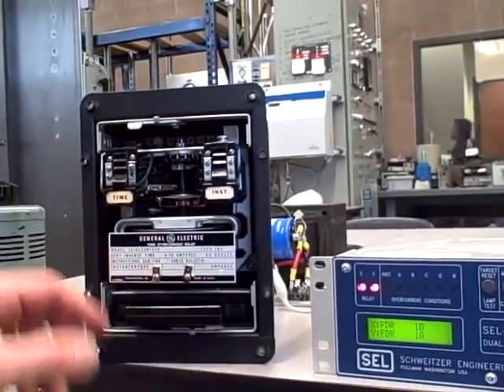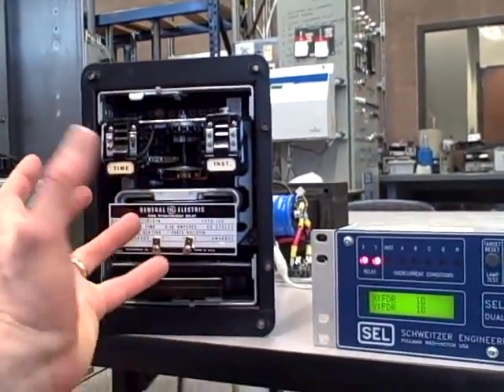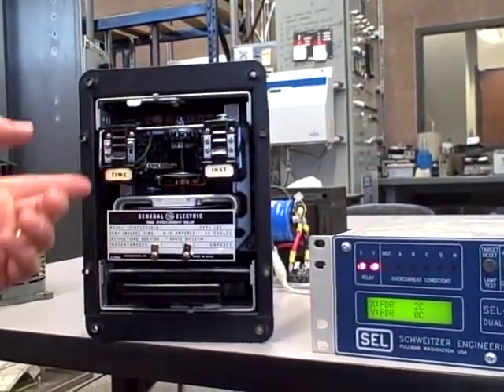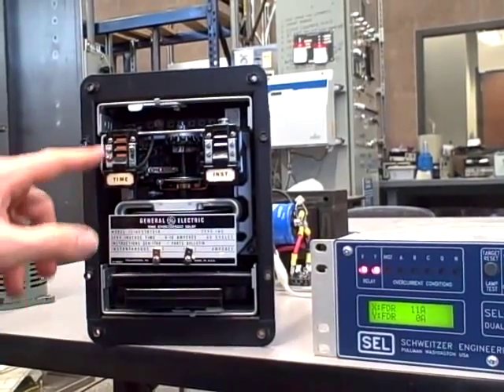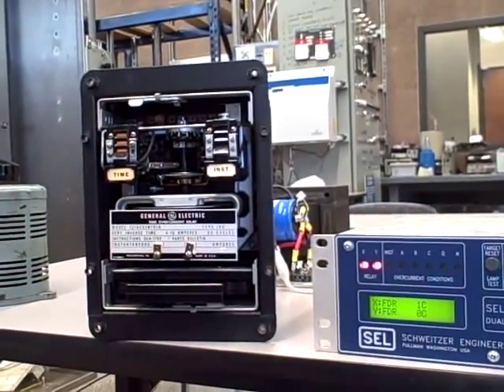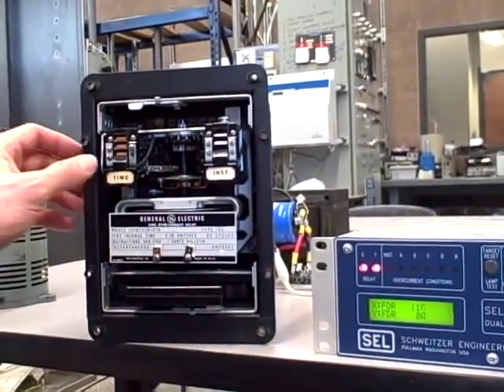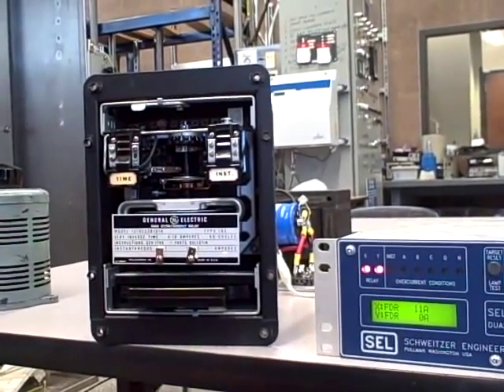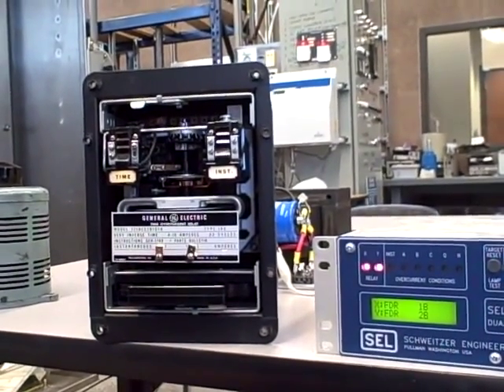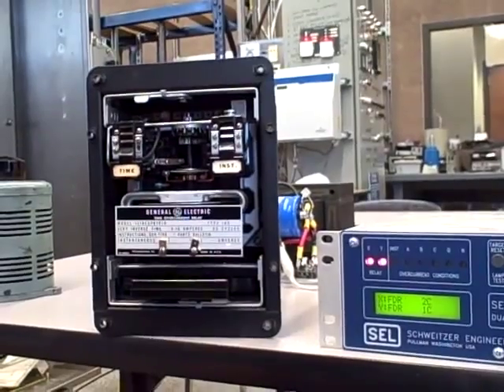If we had a time overcurrent event, that's where the disc would take time to rotate, the peg would touch the contact, and then we'd have a time overcurrent. You'd see the target come up for time overcurrent, and that would trip the breaker after that certain amount of time. So again, very quick review of the electromechanical overcurrent protective relay system.